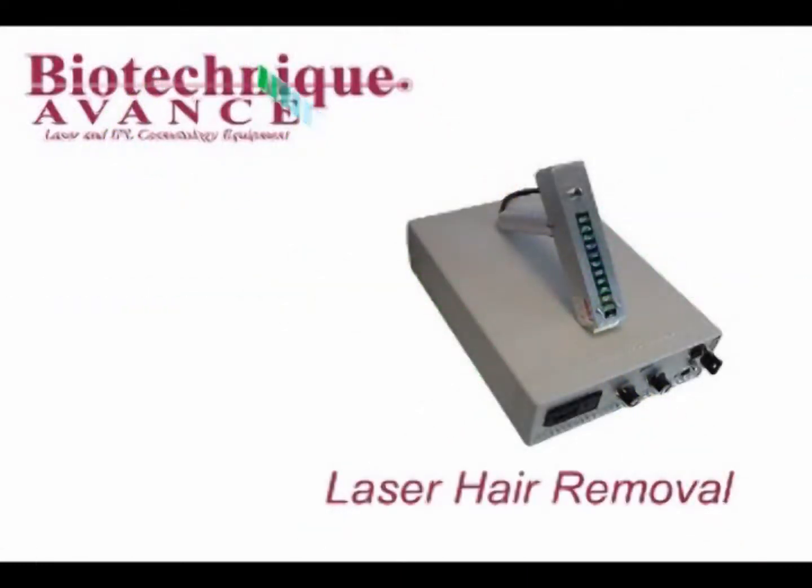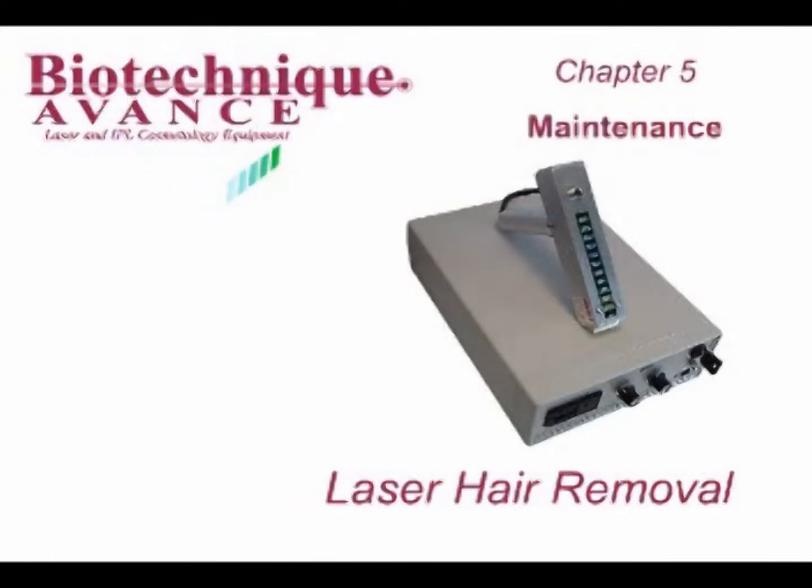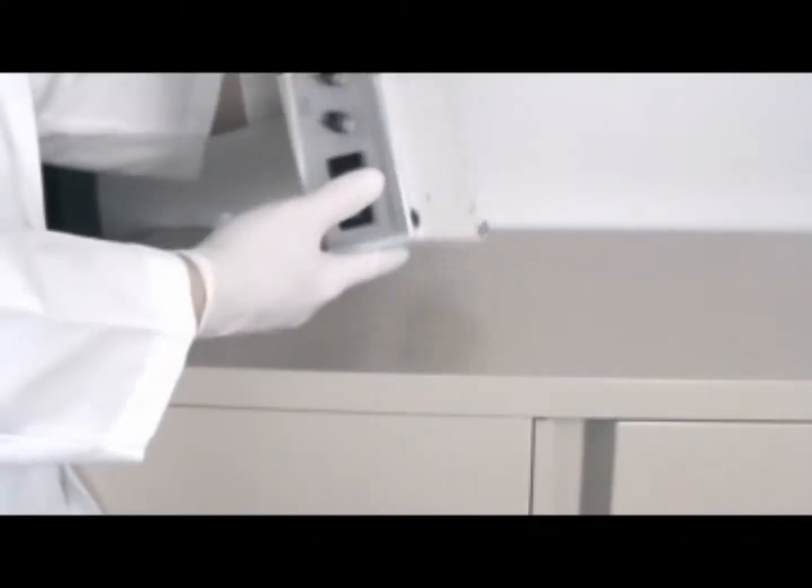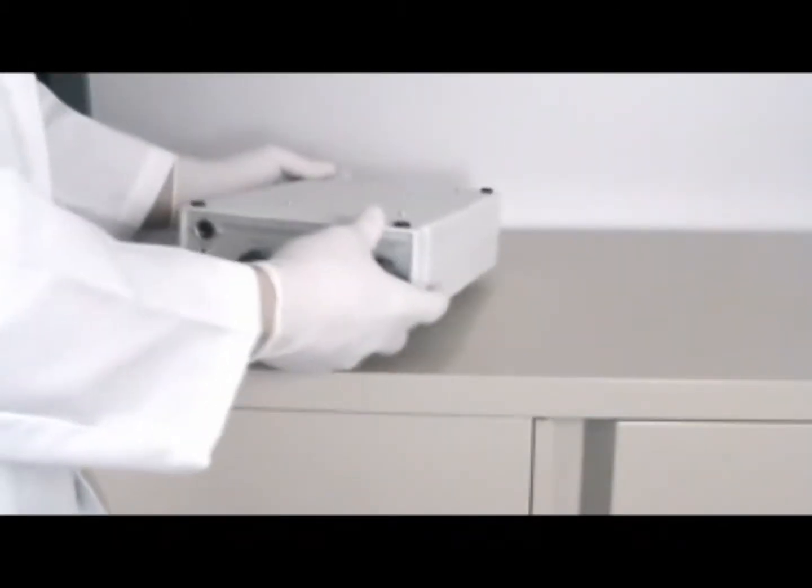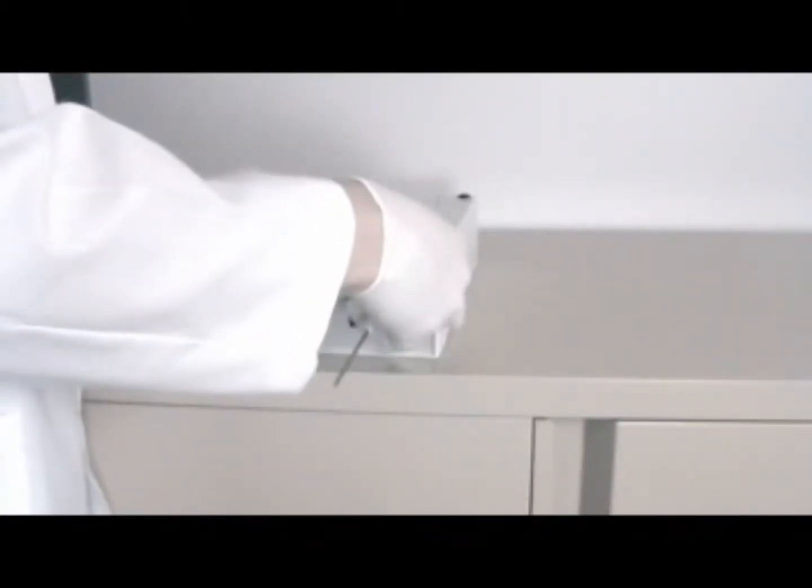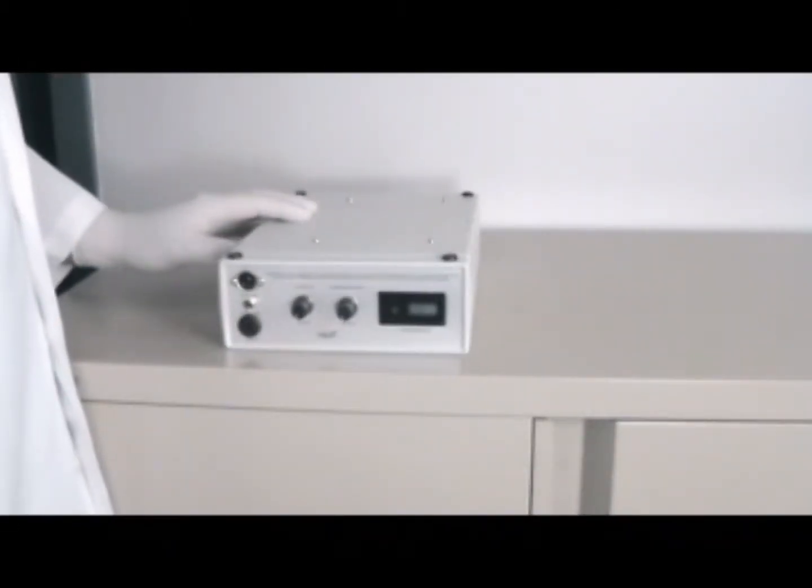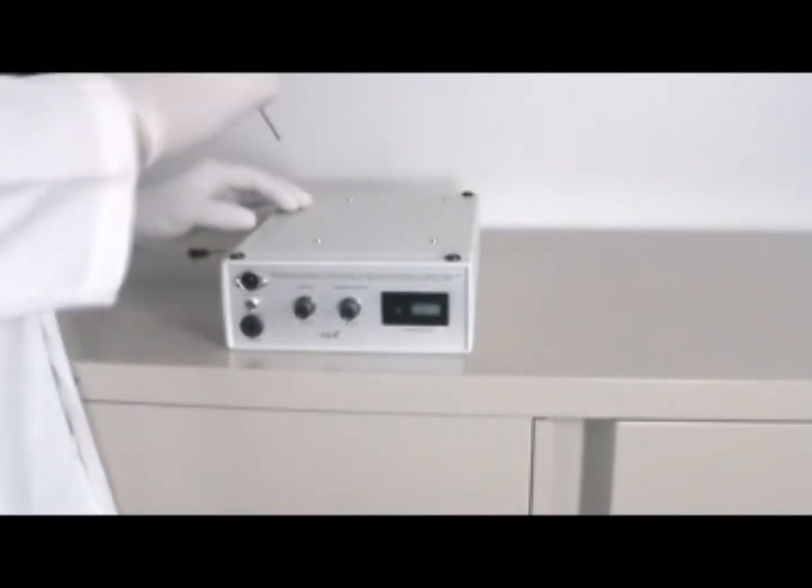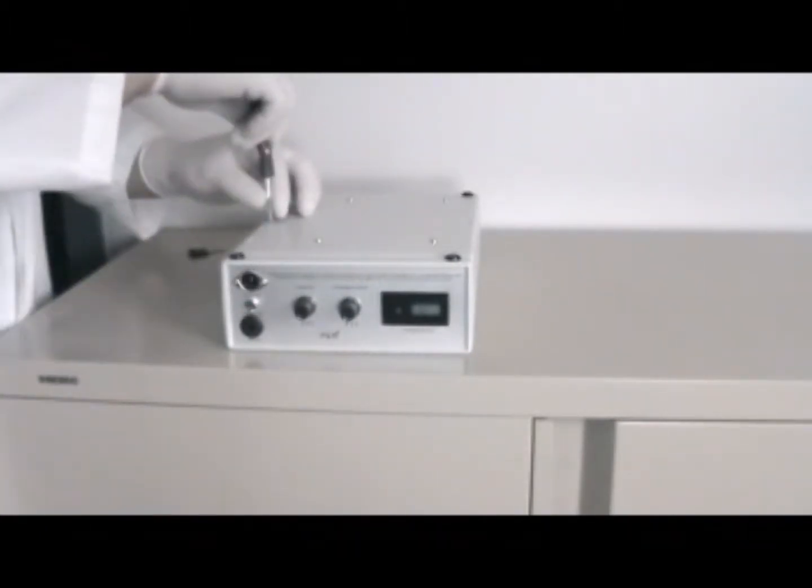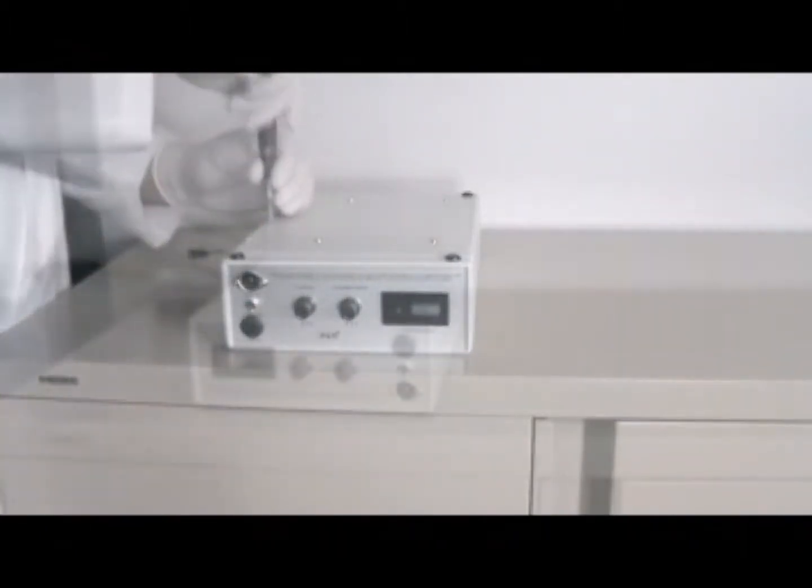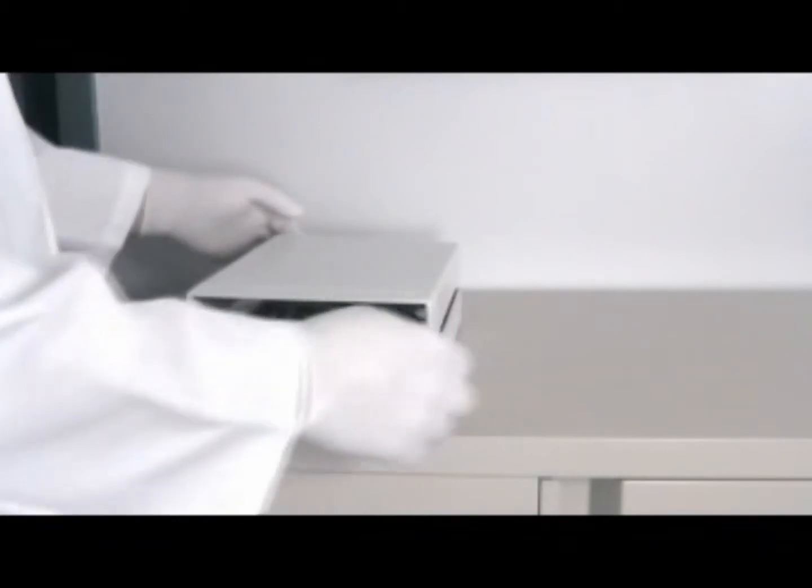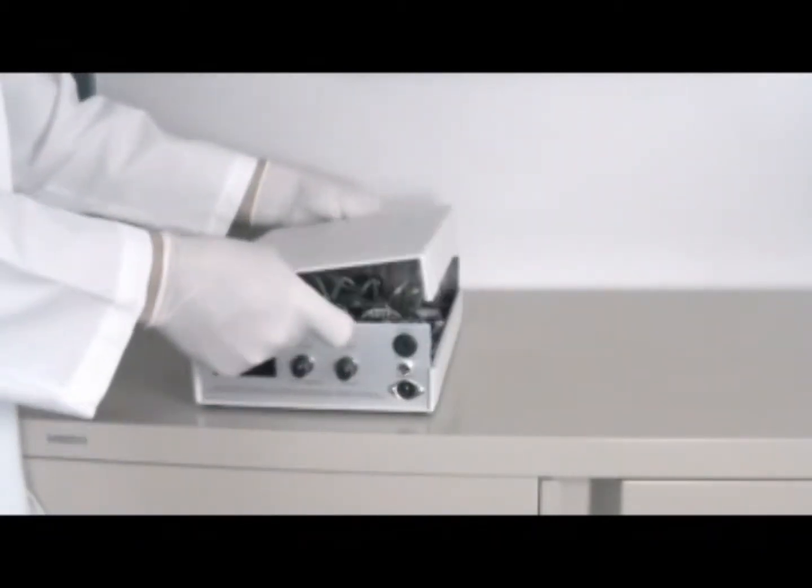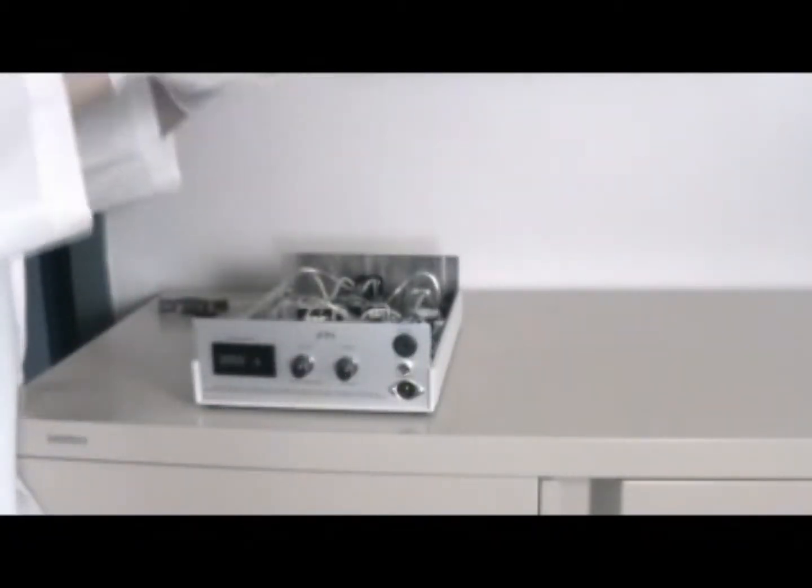Laser hair removal, Chapter 5: Equipment Maintenance. If you're going to be using this unit overseas, you will have to convert the voltage. Remove the two screws from the underside of your driver unit. Remove the top cover as shown.